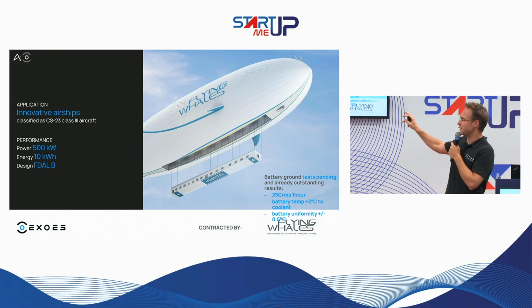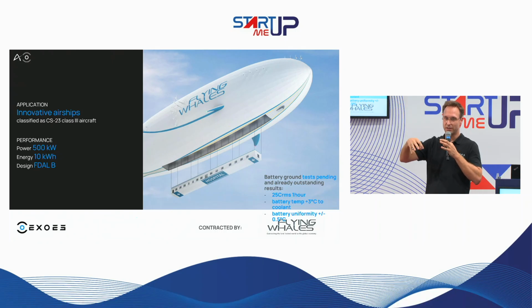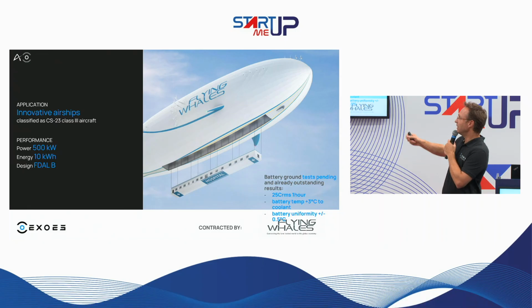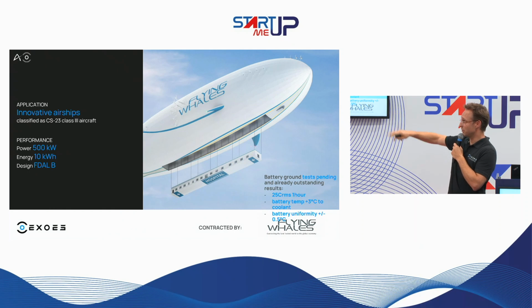So the battery is very specific, this is a hybrid system. You've got a big 1 megawatt turbo generator on board, and 2 megawatts of propeller installed, and in between you need to control the voltage of this grid. This is done by a battery that is really heavily cycled: 500 kilowatts, but only 10 kilowatt-hours of energy, so no interest in energy, but in power.